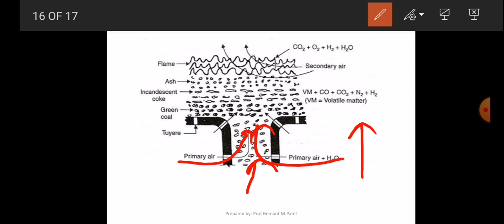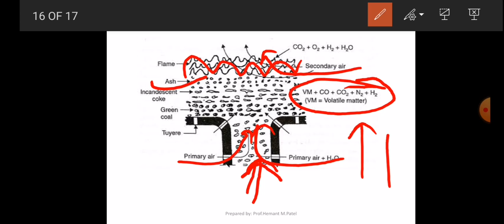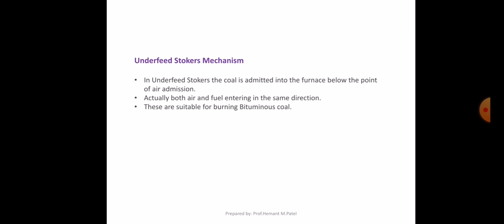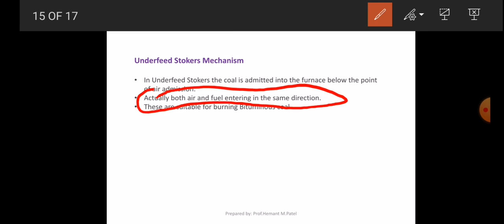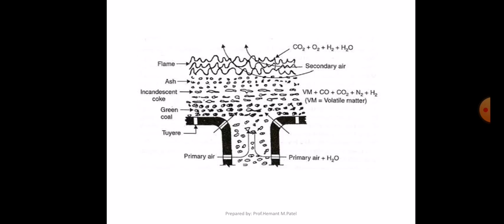So in this figure you can see the coal and the primary air being introduced, both in the same direction. That's why it is called underfeed stoker. Also, flue gas is generated, and this is the flame. Secondary air is required for proper combustion, and this is the VM, meaning volatile matter. Generally in underfeed stoker, the direction of the air and the direction of the coal are the same, that's why it is known as the underfeed stoker. Already we have discussed, both air and fuel enter in the same direction. Okay, so this is the underfeed stoker mechanism. Thank you.